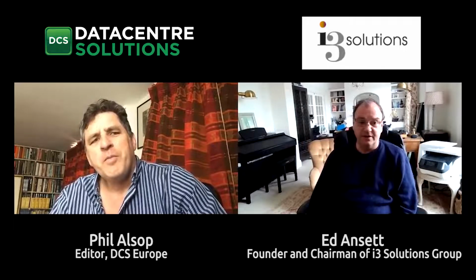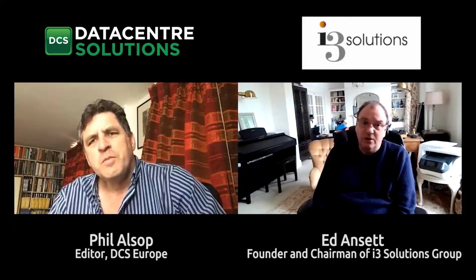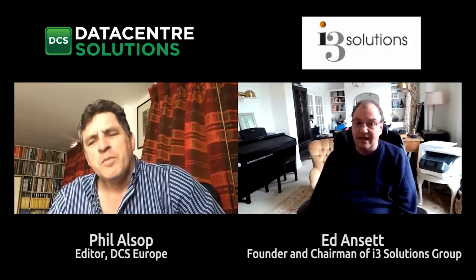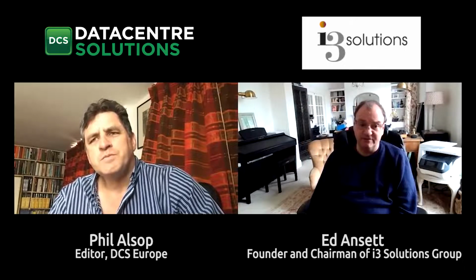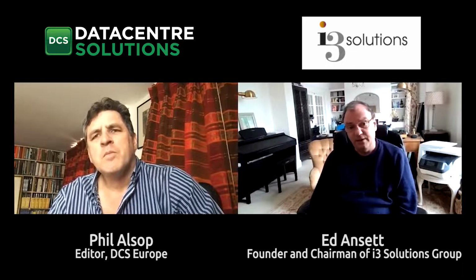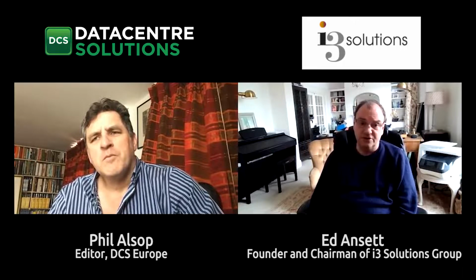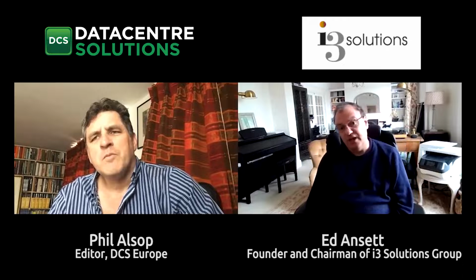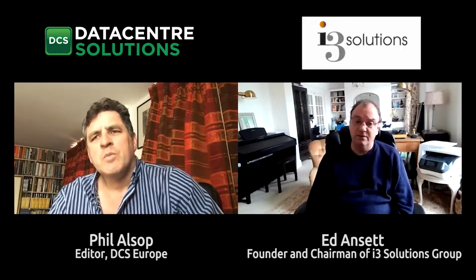Okay, so this is definitely an upside for data centers. This is essentially integrating the data center energy systems with the grid. Currently, the way data centers interact with the grid, generally speaking, is they take power from the grid, condition it through a UPS system, and use standby diesel generators as backup power. So essentially, there is no proper integration with the grid - the data center does not export power to the grid and typically doesn't isolate itself from the grid when the grid has demand issues.